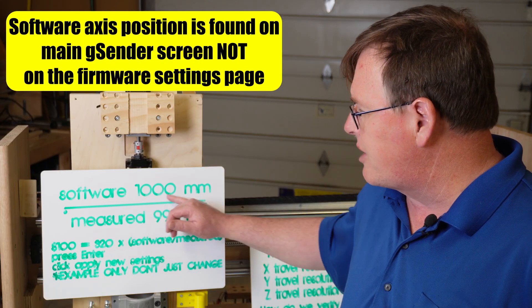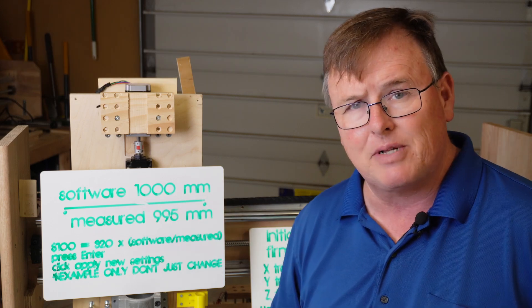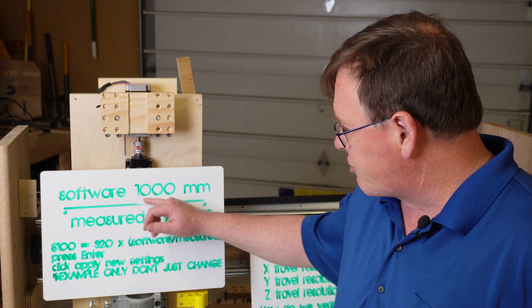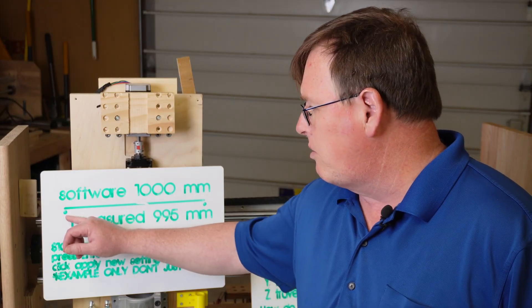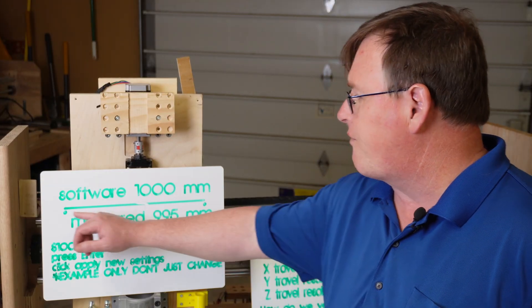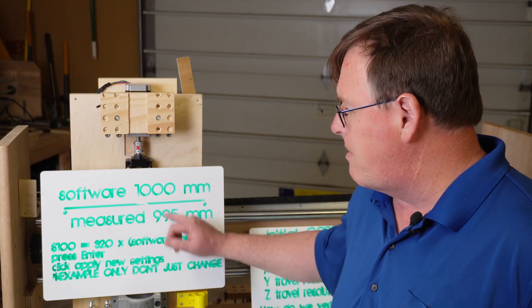And we'll measure the actual distance between the marks and compare that to the software distance. Your software then on your screen should have some value. I just chose 1000 for simplicity here. But whatever your screen has, that'll be your software value. Then you need to take a ruler or something and measure from the center of the dot to the center of the dot and see if those two values match. If they match, you're good to go.